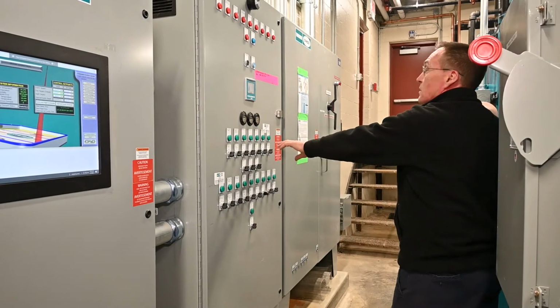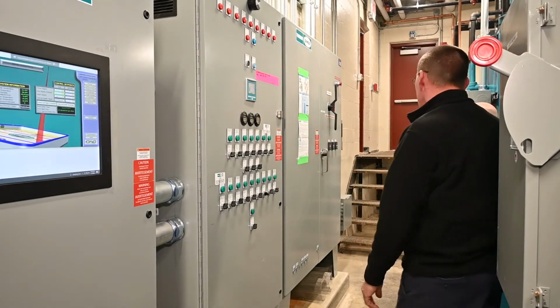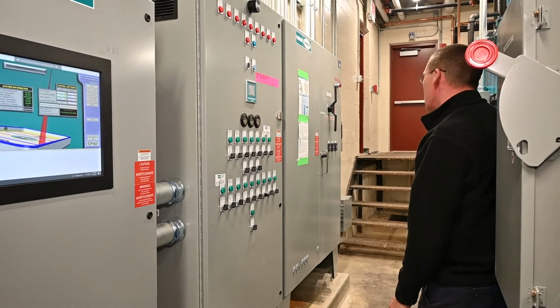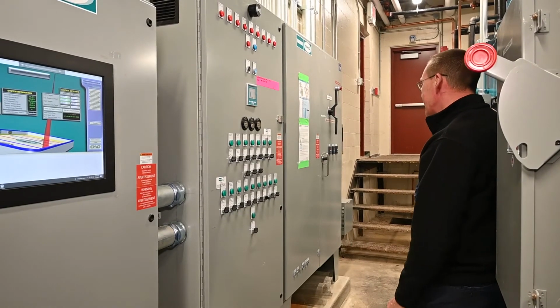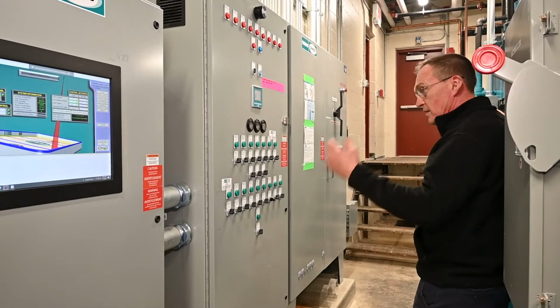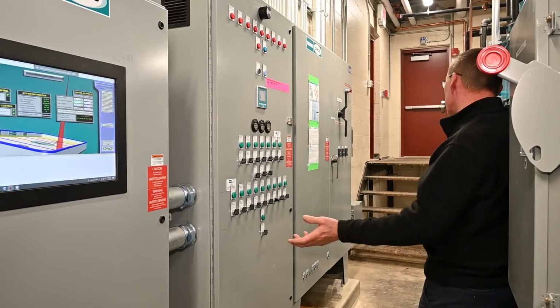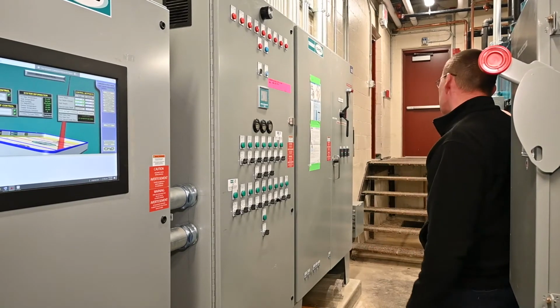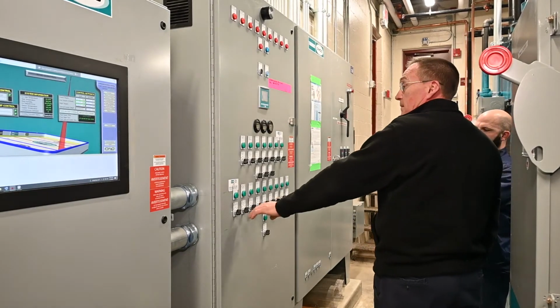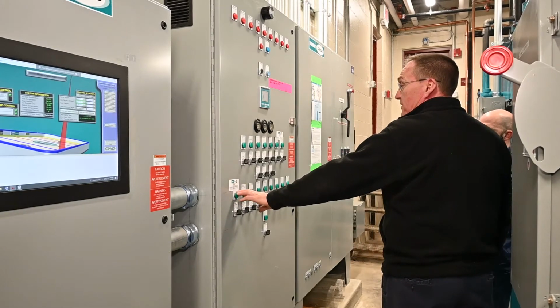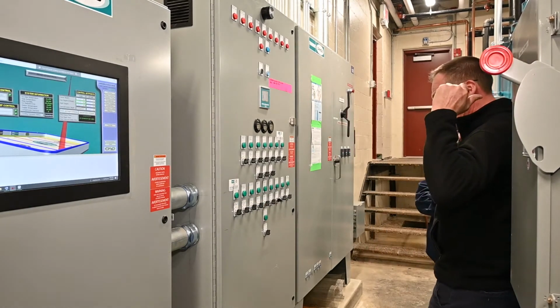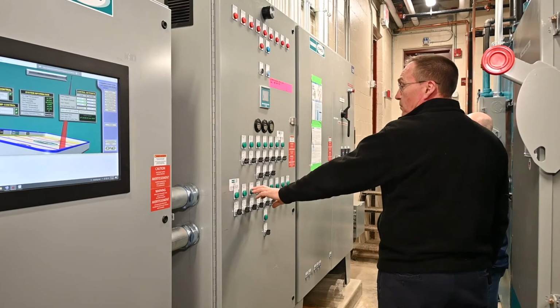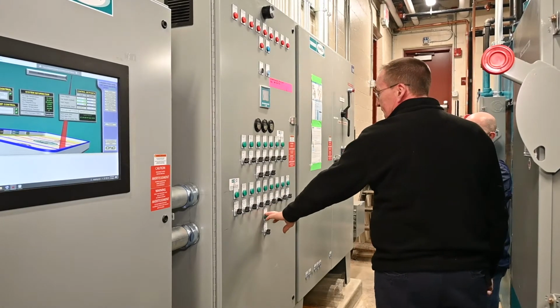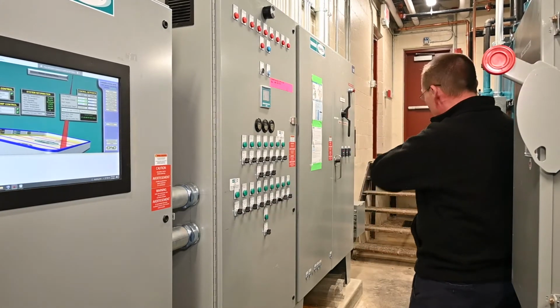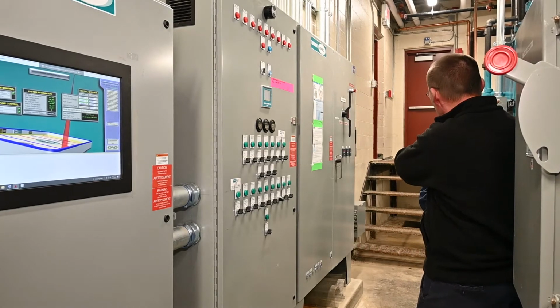If you put this compressor switch into hand and the computer is not calling for it, it will generate a DDC alarm. Computer says, hey, you're not supposed to do that. Why are you doing it? And it will make that buzzer go off and generate that alarm. Cooling tower water pumps, P5 and P6, those are the ones attached to the sump tank. Subfloor pumps, P9 and P8 down here. Those are the two pumps mounted high up on the wall for your subsoil heating.